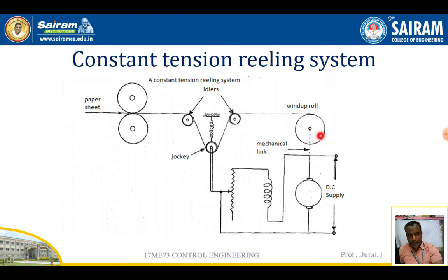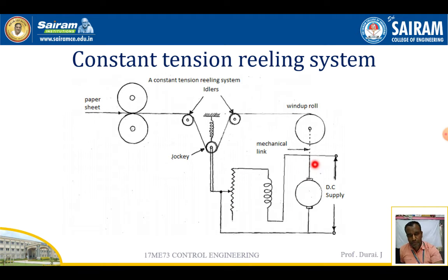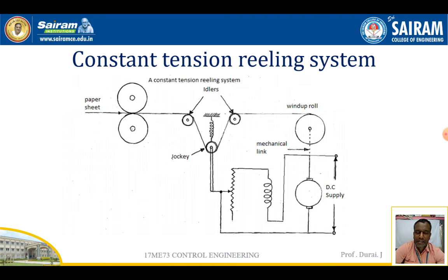They maintain constant tension over the paper sheets and produce good paper rolls. As the paper sheet comes through, the jockey movement — moving up or down — changes the field current, which is used to run the motor and increase or reduce speed to maintain constant tension. This is how the constant tension reeling system works.